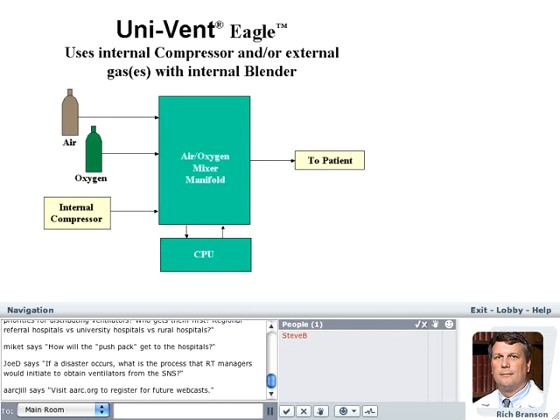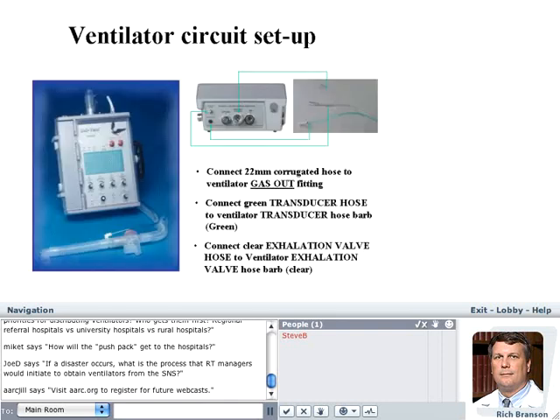The 754 can do the same thing the LP10 does, which is you can have the air bleed in, or it will work with high pressure air and oxygen, which you kind of see here in the system, that it will take both 50 psi air or 50 psi oxygen. If you don't have the air, the internal compressor will run by itself, and if you have neither, the internal compressor will run, and then you'll have to add oxygen to the circuit. Very similar to the way you do the LP10.